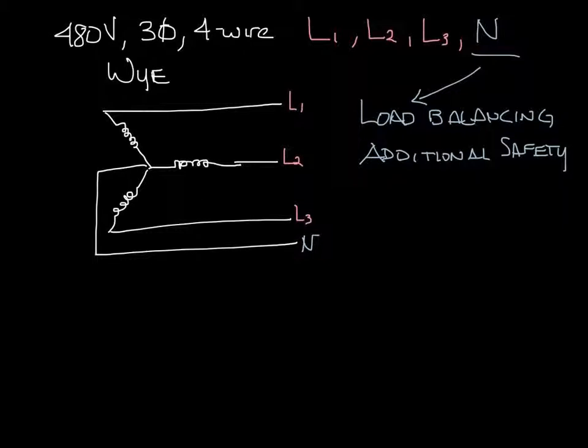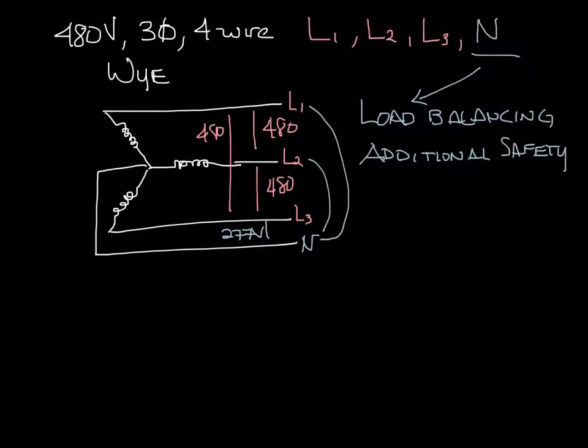With the 4-wire Y, you can get 480 volts line to line. So between L1 and L2, 480 volts. L2, L3, 480 volts. But you can also get 277 volts between any line and neutral. So L1 to neutral, L2 or L3 to neutral is 277 volts. The lower voltage is always the higher voltage divided by the square root of 3.